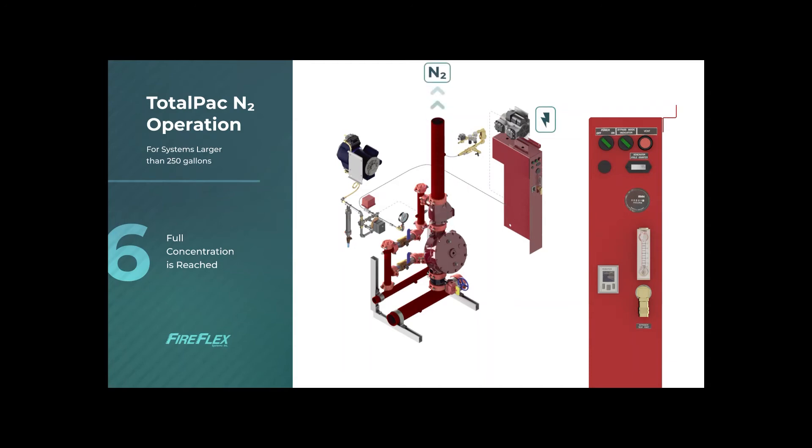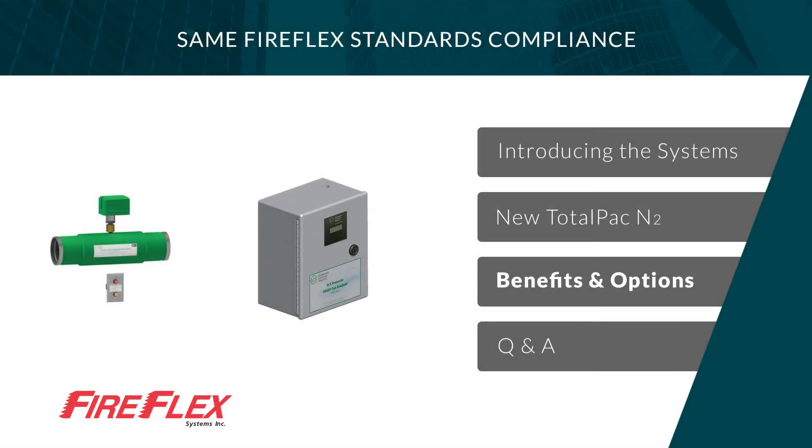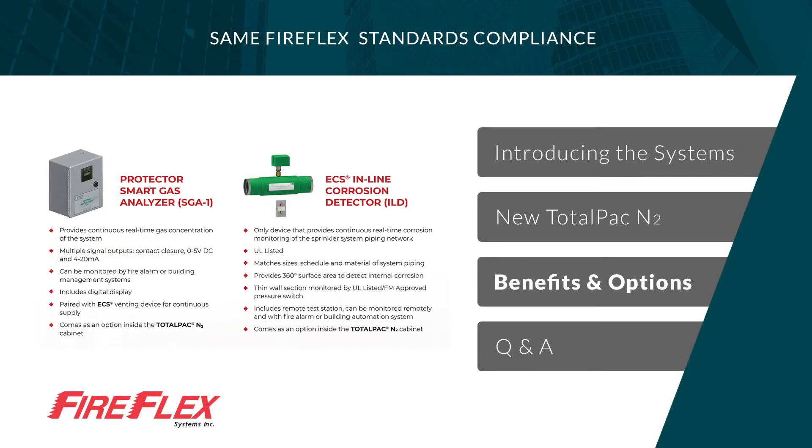A nitrogen purity reading can be taken to verify purity at the end of the process, or this can be achieved using the smart gas analyzer for real-time readings. There are many options in the TotalPac N2 for corrosion monitoring and measuring. One such device is the ECS inline corrosion detector, designed to provide early warning indication that the corrosion rate within system piping is at an unacceptable level. Its unique design features an externally milled section covered by a welded sleeve to create a monitored pressure chamber. If the thin wall section fails due to corrosion, the pressure switch gives a signal. This device can be wired to the TotalPac N2 and is offered in multiple sizes, materials, and pipe schedules.